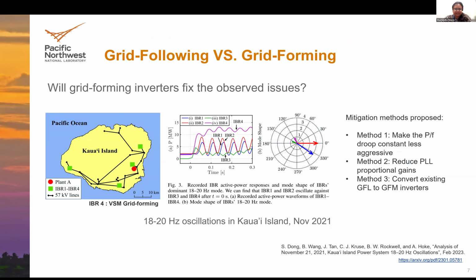So one question arises here: if instead of grid following inverters, we install grid forming inverters, are these observed issues going to be fixed? So the answer is yes, some of them may be fixed, especially the ones related to grid strength. Yes, with grid forming inverters, some of these issues will be fixed. But issues arising due to improper plant control logic may remain, for example, with virtual synchronous machines, where setting the inverters is more complicated than, say, droop-based grid forming inverters. So the more complicated the logic, the more difficult it is to set or tune parameters, and that may lead to issues again.